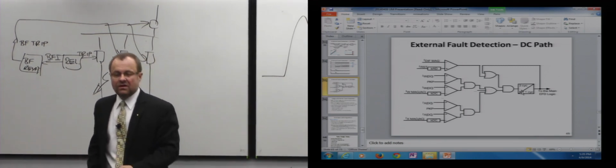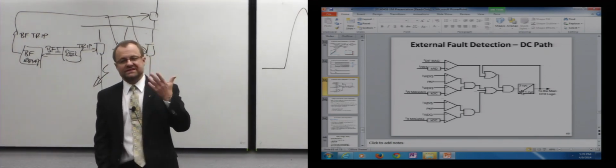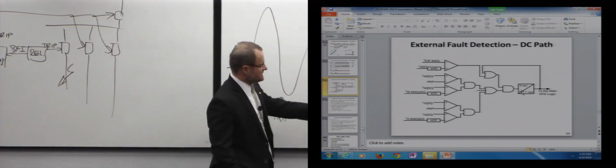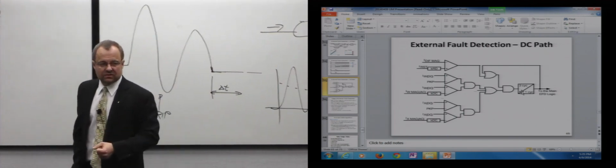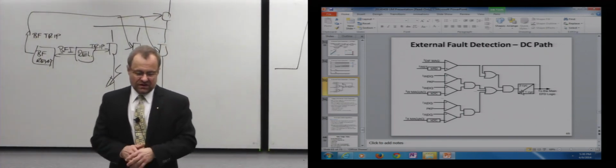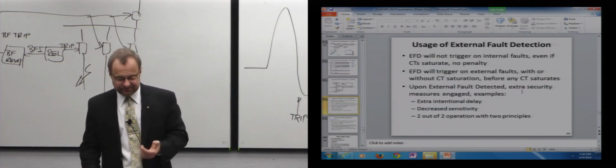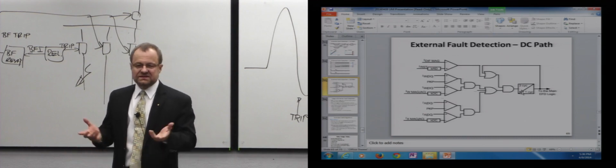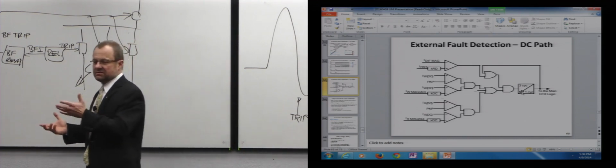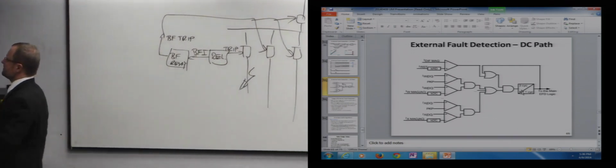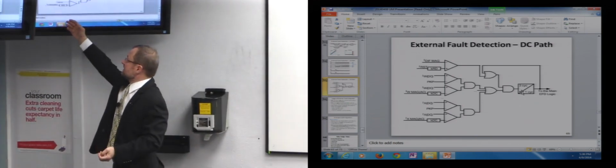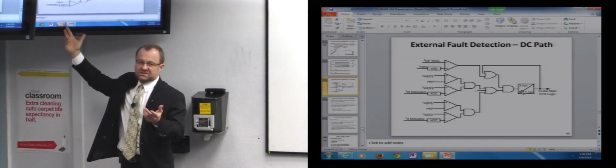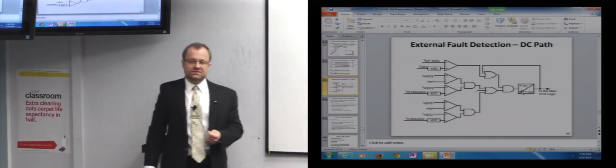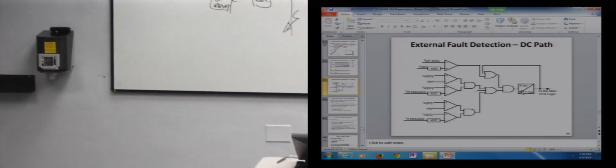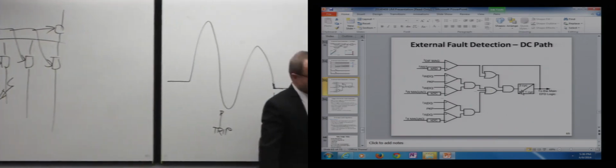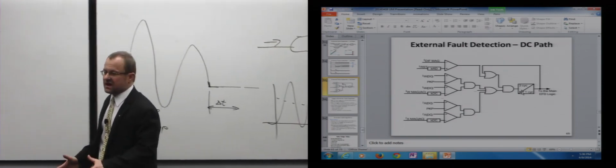So I have to seal it in or go on a long timer to the tune of a second or something, knowing that this thing will settle after a second or two, and I will go back to my normal sensitivity and normal situation. So again, what this example showed is, do I use anything fancy? Did I spend months researching some Kalman-based estimators? No, I used a simple thing. How do I measure DC? Just average it. How do I measure that AC magnitude? Anyway, I mean, this is not a fast thing. I wait for 3 cycles. I know that those CTs are not going to give up on me that fast. It will take a while for that DC to kill my CTs. So I have time to deal with it, right?